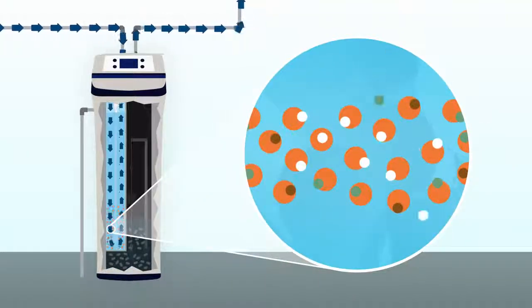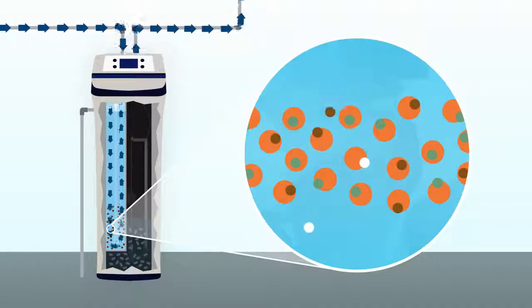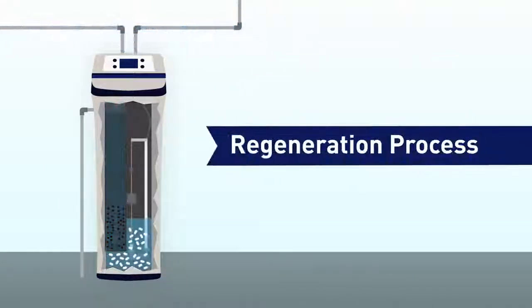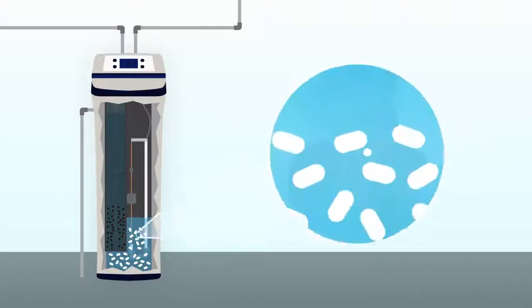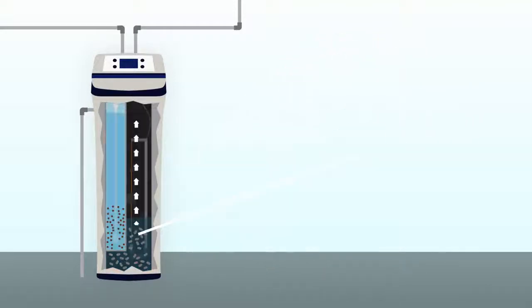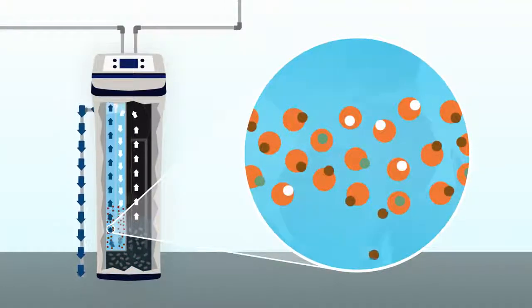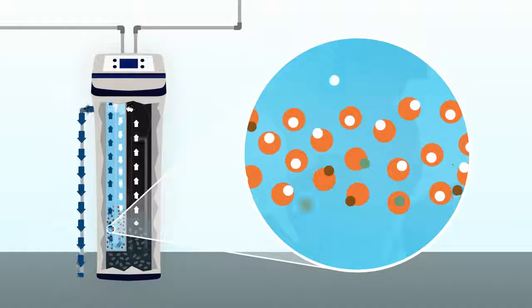When the beads are coated in calcium and magnesium, it's time to regenerate, or clean, the beads so that they can continue to work their softening magic. This is where salt comes in. The salt you add to your softener creates a brine solution that is held in a small reservoir. The brine is pumped into the resin tank to remove the hardness minerals from the beads. Once recharged, the beads are ready to soften more water.